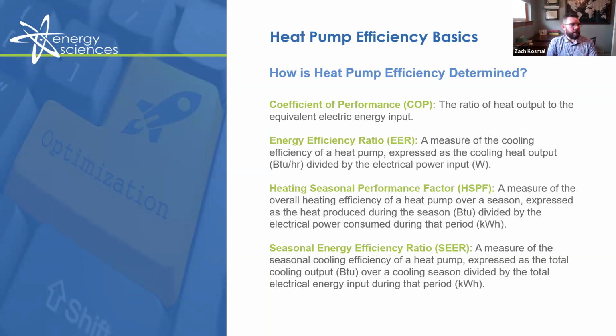And lastly, we have the seasonal energy efficiency ratio, or SEER. This is a measure of the seasonal cooling efficiency of a heat pump expressed as the total cooling output in BTUs over a cooling season divided by the total electrical energy input during that period in kilowatt hours. So to determine SEER, manufacturers typically will test the equipment at various loads. For example, full load, 50% load, 25% load, etc. And they weigh those results based on typical usage patterns.